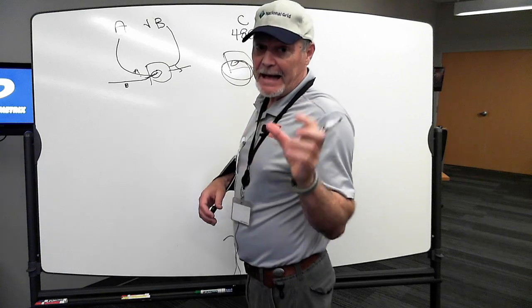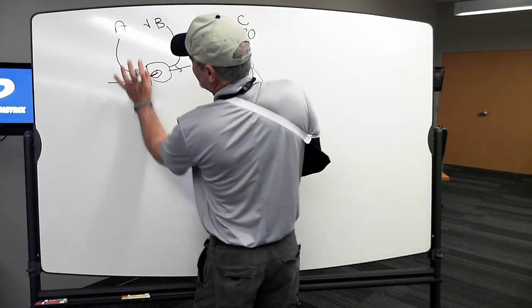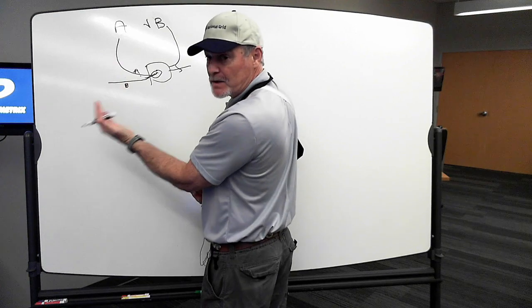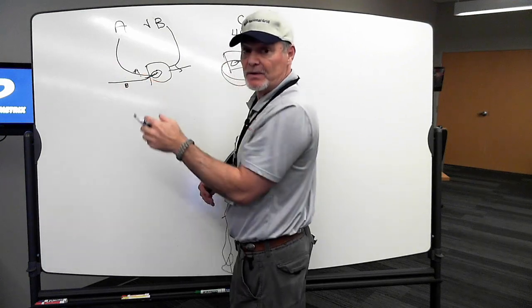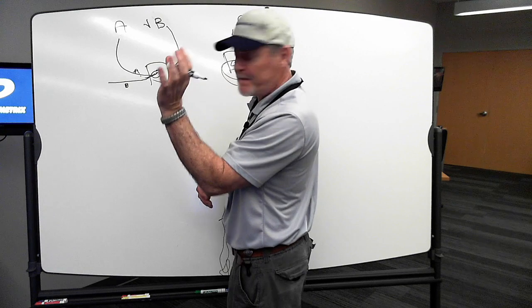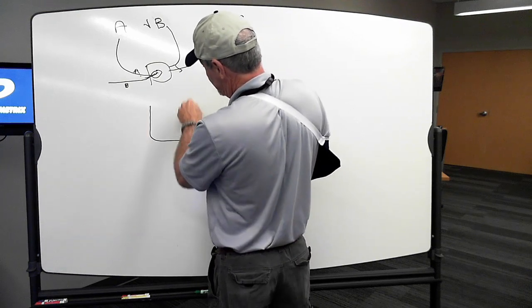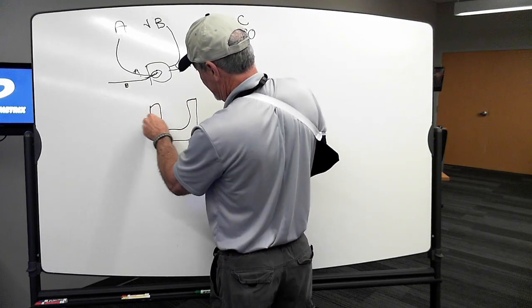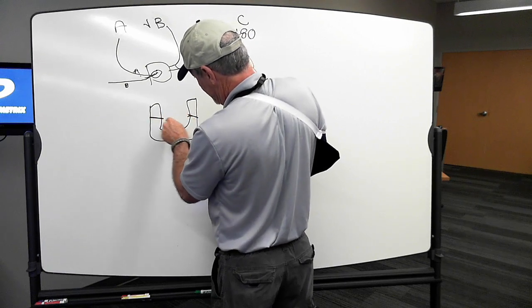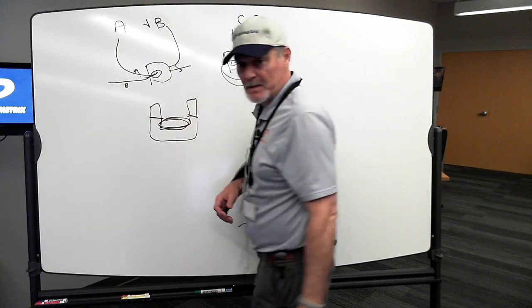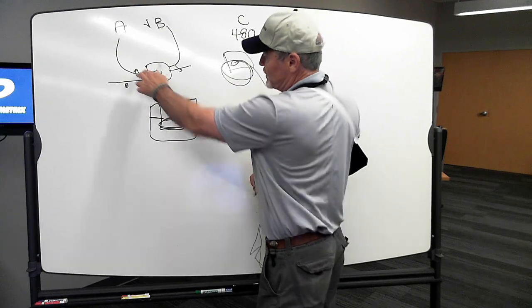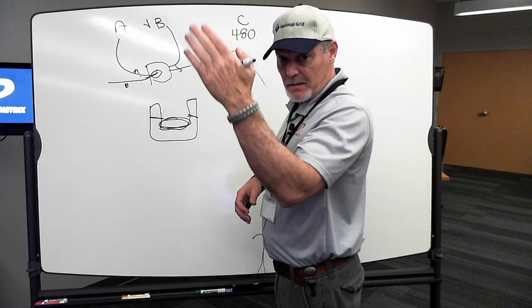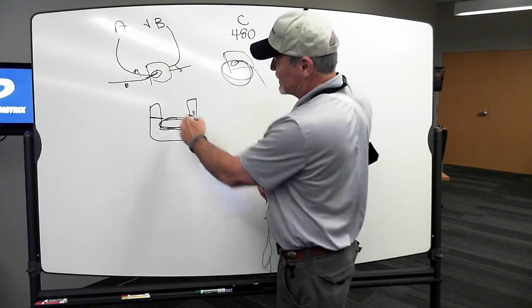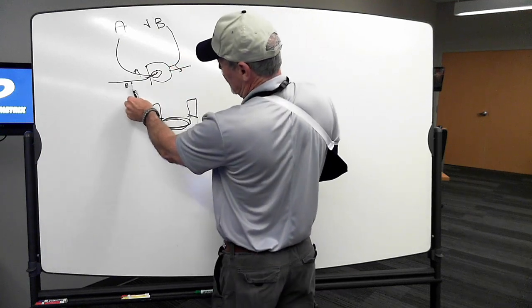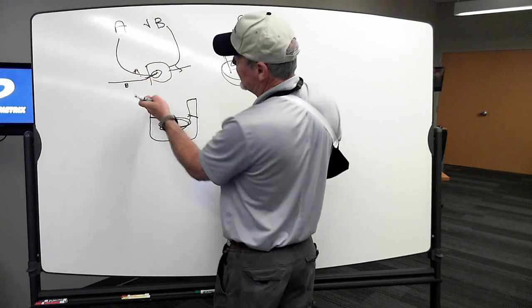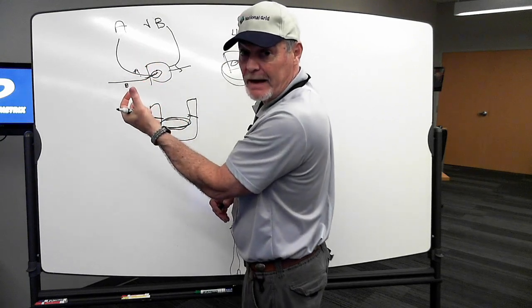So if I have a high volt probe, I need to get up there and get on both of them like this. I want to try and get as close to the CT as possible because my two conductors are as close as possible, to be able to get them both up in there. Because remember, a high volt probe has a line right there, and you want to be in this spot right there - that's your sweet spot. You want to get both those conductors, two lines on that high volt probe, beneath there, but inside your window. So you're going to want to get closer to where the two of them are closer together so you can grab around both of them at the same time with a high volt probe.